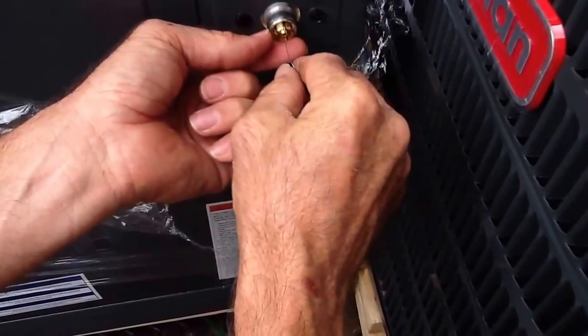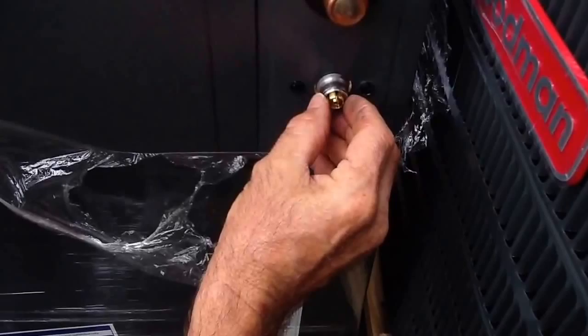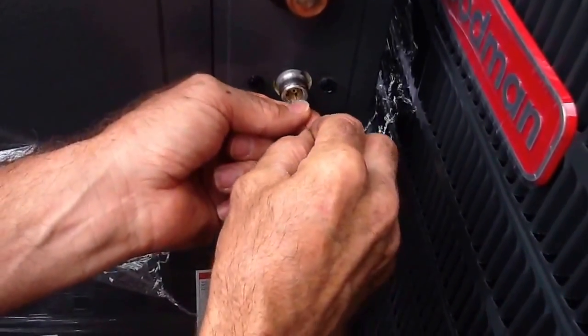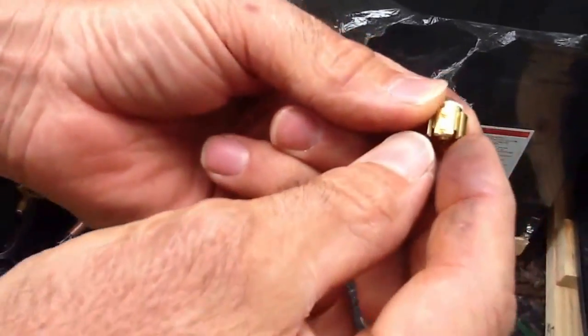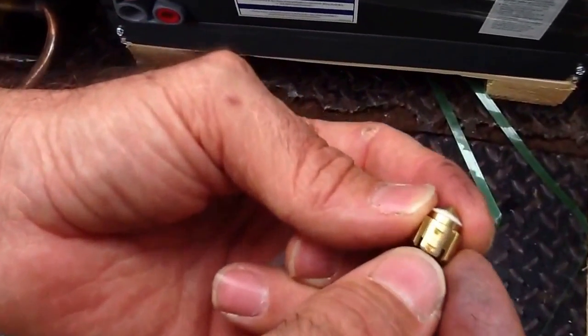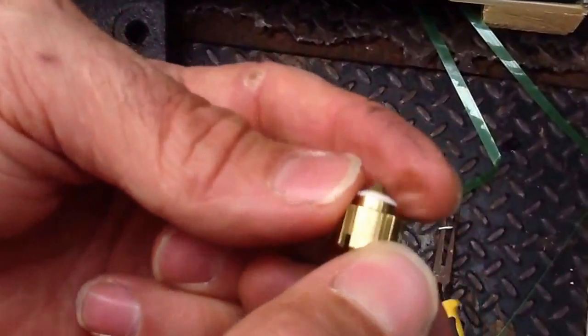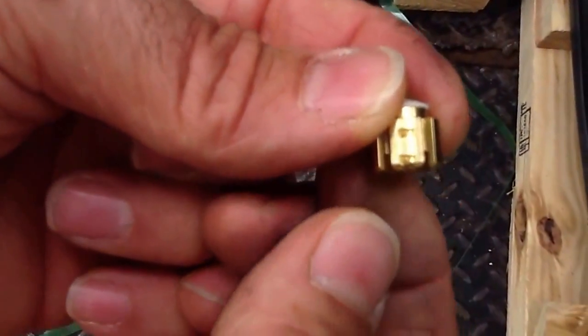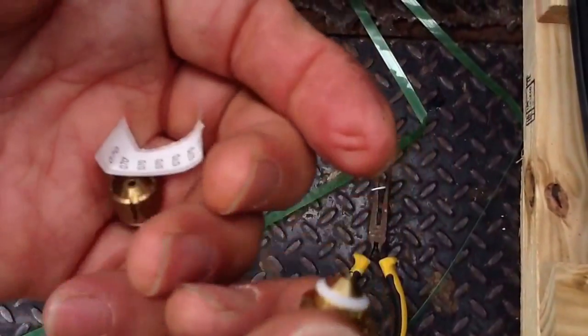Sometimes a bobby pin works. Now I want you to notice how it comes in — it comes out right. So I'm going to grab the piston very carefully. What size is this piston? We're going to roll it over here and look — it looks like a 71. Can you see that? 71. All right, this is a 70.